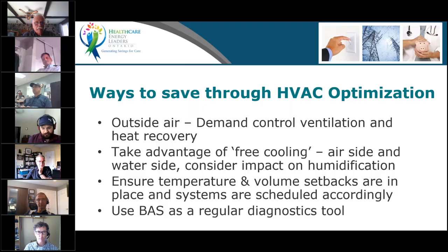And then there are the other measures, such as demand control ventilation and heat recovery. And here we're not talking about chiller heat recovery. I know there's somebody, I think from Vancouver or Edmonton, that is right now using chiller heat recovery. That will be discussed in the next module. Here we're talking about outside air heat recovery. Demand control ventilation, it depends. You cannot use it in many of the systems. If you have type 1 and type 2 spaces, usually you leave DCV, demand control, alone. That will be for type 3 spaces.